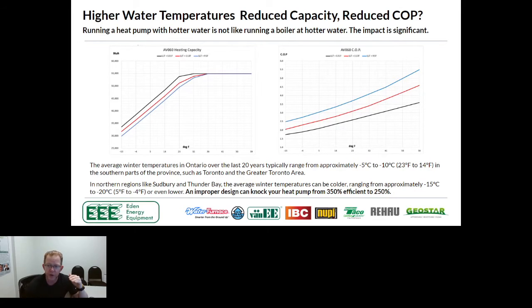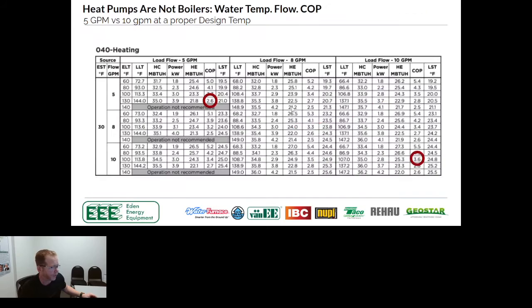So you potentially could take a unit that should have a COP of 3, which is 300% efficient, and give it a COP of 2 or 2.5 just by not putting the right size piece of copper on it. So the question of $20 of material or a 30-second phone call to your supplier of, hey, what's the flow rate? What should I be piping this in? You can make a negative impact on this system for the entire life of that system.